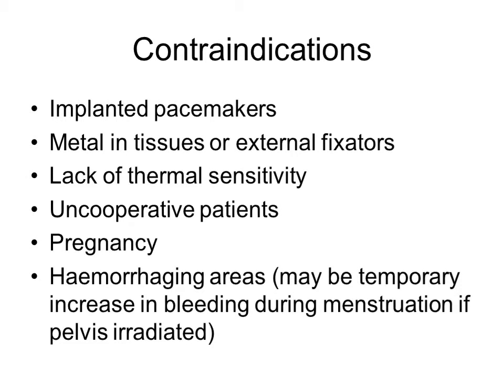Contraindications are as follows. Particularly important are metal in the tissues, which may be heated preferentially, and pacemakers, which may be disrupted by the electromagnetic field. It is recommended that other electrical equipment is kept at least three meters from the machine during operation. This is why most departments ask patients to inform the physiotherapist or reception desk if they have a pacemaker or hearing aid. It is also why hospitals insist that mobile phones are switched off, as the radio waves emitted may interfere with electrical equipment.